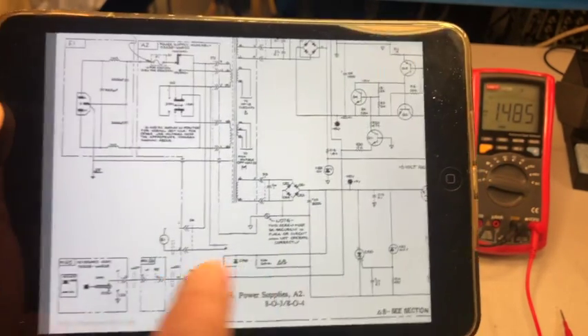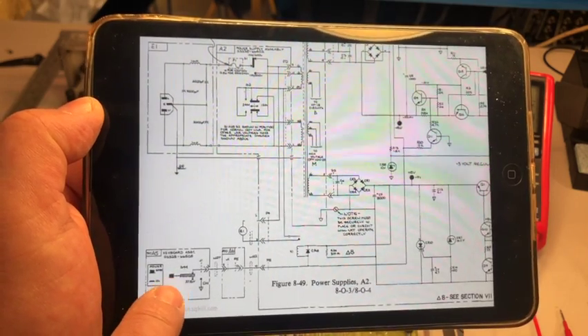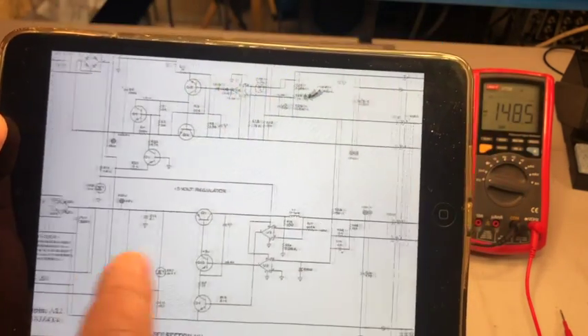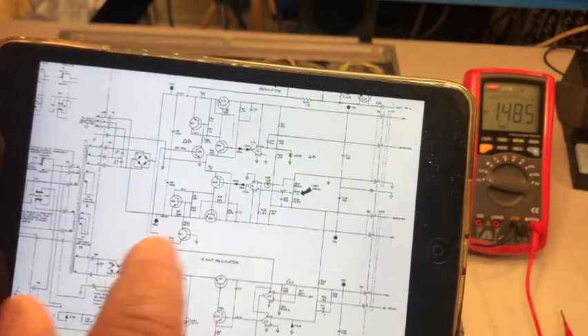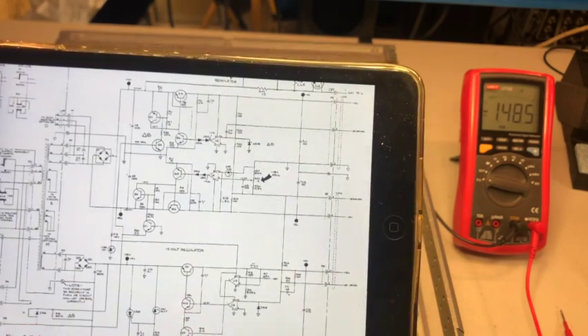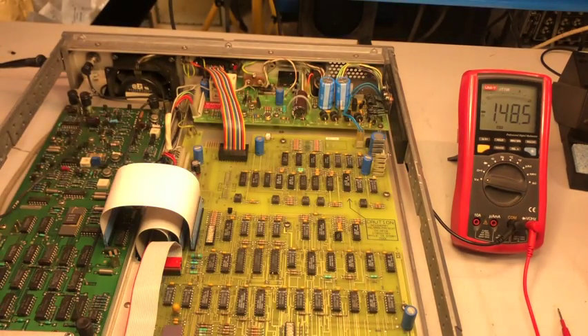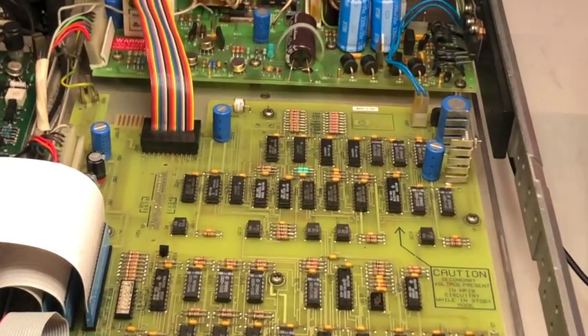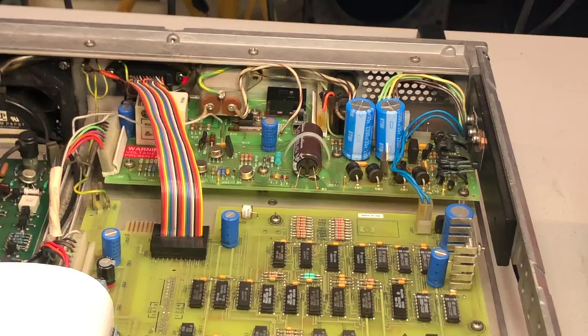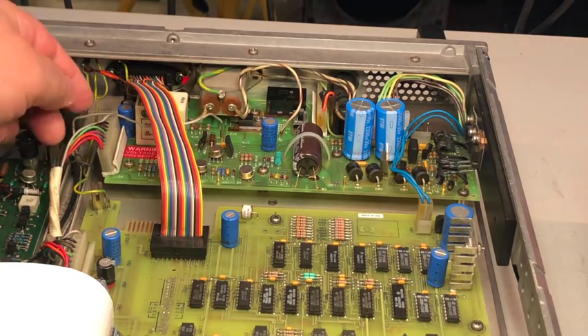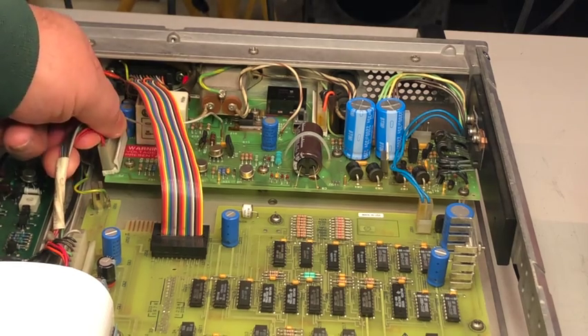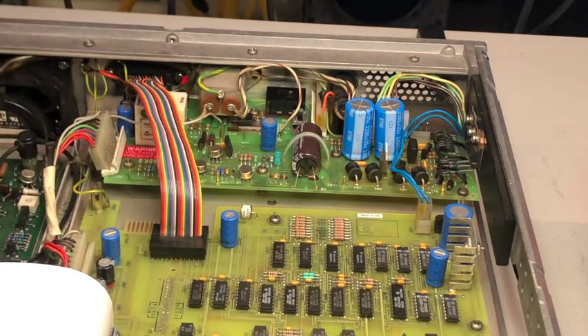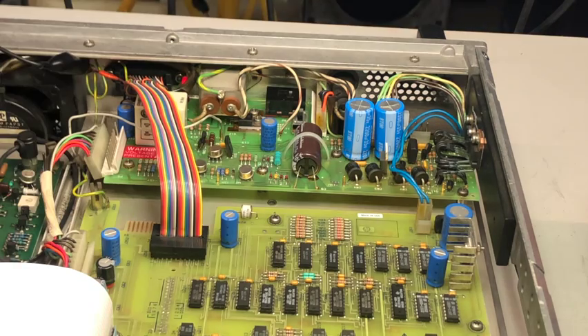That is driven by the soft start push button in the front panel. The service manual gives a very short indication and suggests removing P5, which is the output plug, exactly this. Removing that will prevent the power supply from switching on through the front panel power switch. So it suggests making a short bridge between pin 10 and ground.